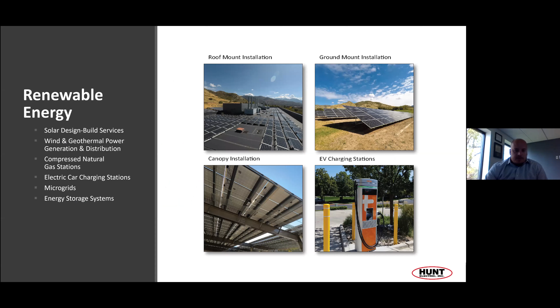When we look at energy storage, we really see 3 key functions, and Kate hit on this also. First is islanded mode, where you can isolate your house or building completely from the utility — disconnect, and the building doesn't know any different. Everything still functions electrically as it should; it doesn't care where the power is coming from. You have a completely islanded, multiple distributed energy resources system, whether it's solar, wind, or heat pumps, coupled with some sort of energy storage. There's lots of variance, but island mode essentially operates completely isolated from any utility connection.